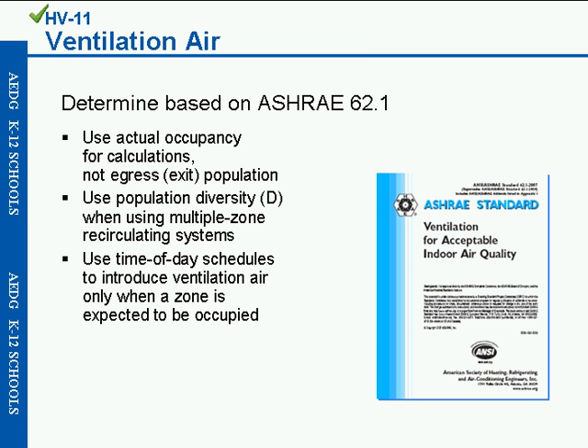The first one is HV11, which refers to ventilation air. There are good design practice recommendations on how to size your outdoor air system, and one of those is to use the actual occupancy of the school for your outdoor air calculations and not the egress or exit population to size your outdoor air system. Another good design practice is to use population diversity when sizing a multiple zone system, as well as using time-of-day schedules to introduce ventilation air only when a zone is expected to be occupied. It's a fairly basic way to do demand control ventilation based on time of day and expected occupancy, and it's the baseline standard recommendation for all HVAC systems provided in the school's design guide for ventilation control.